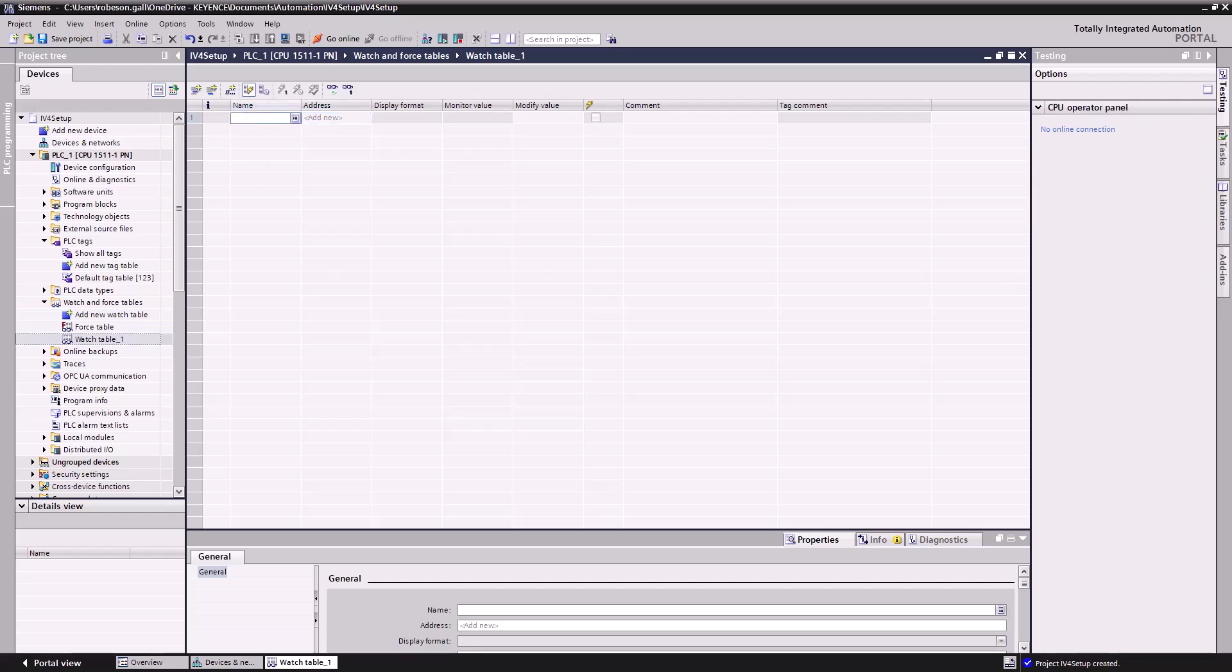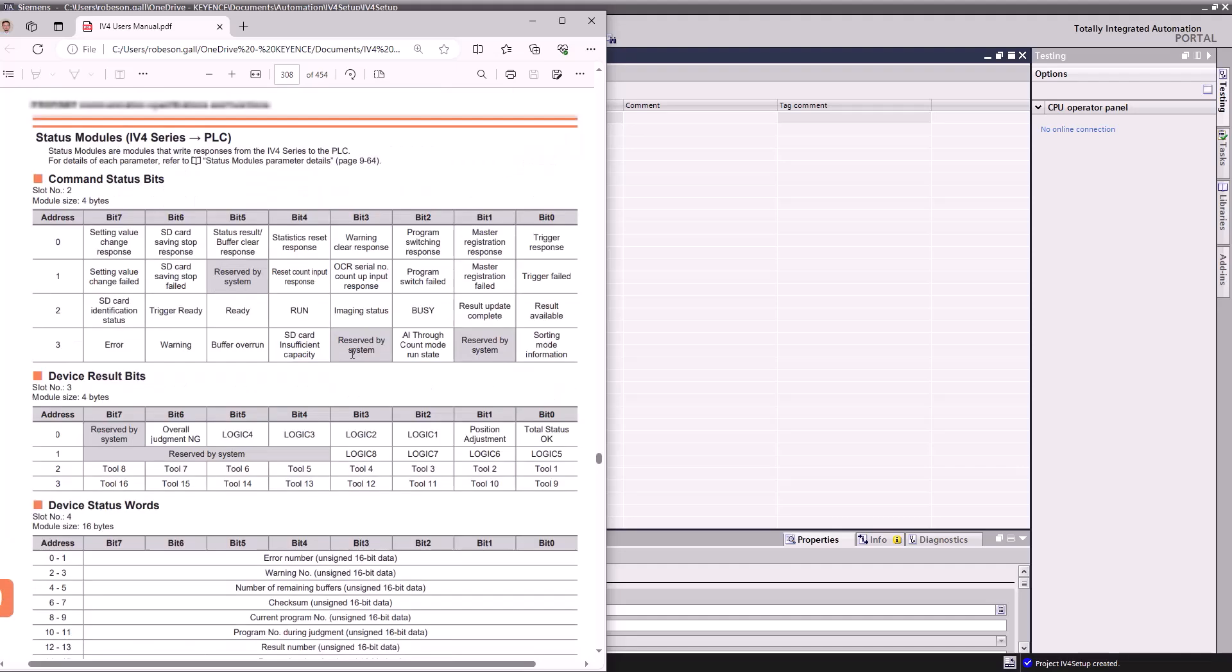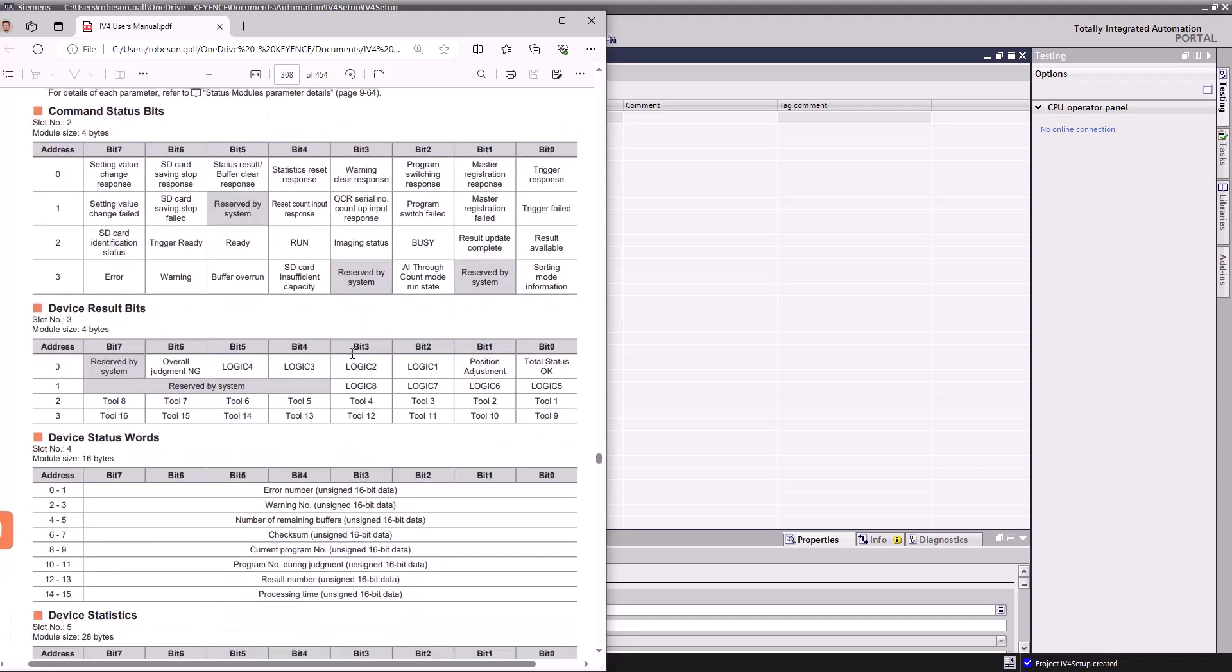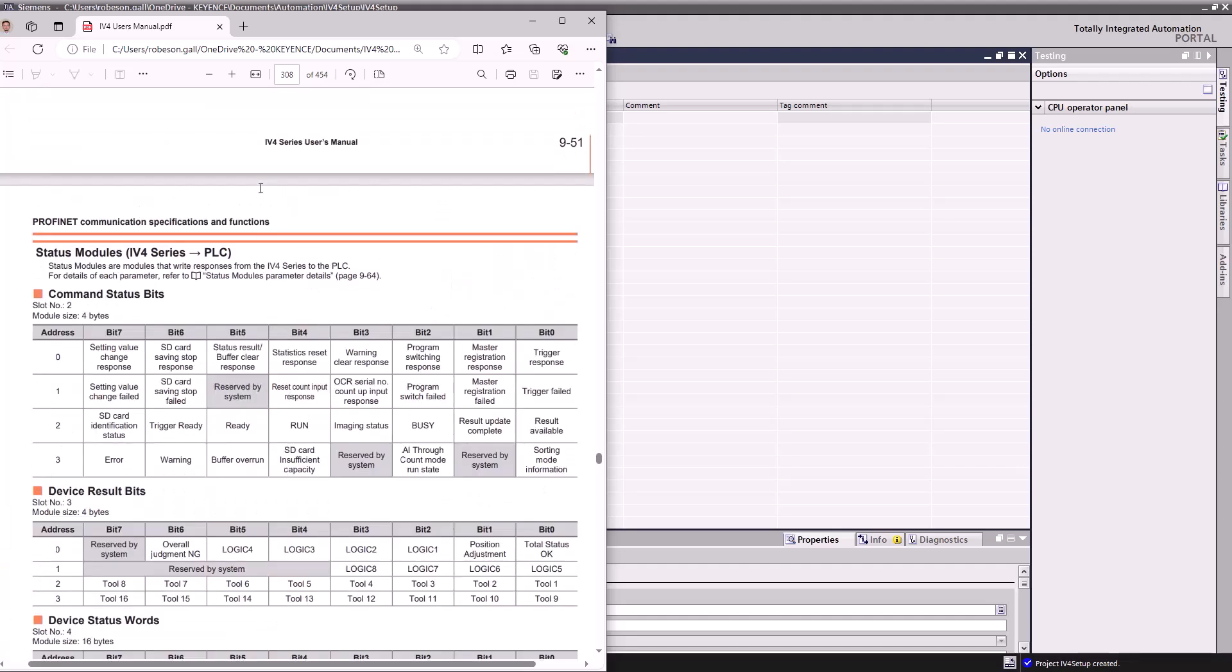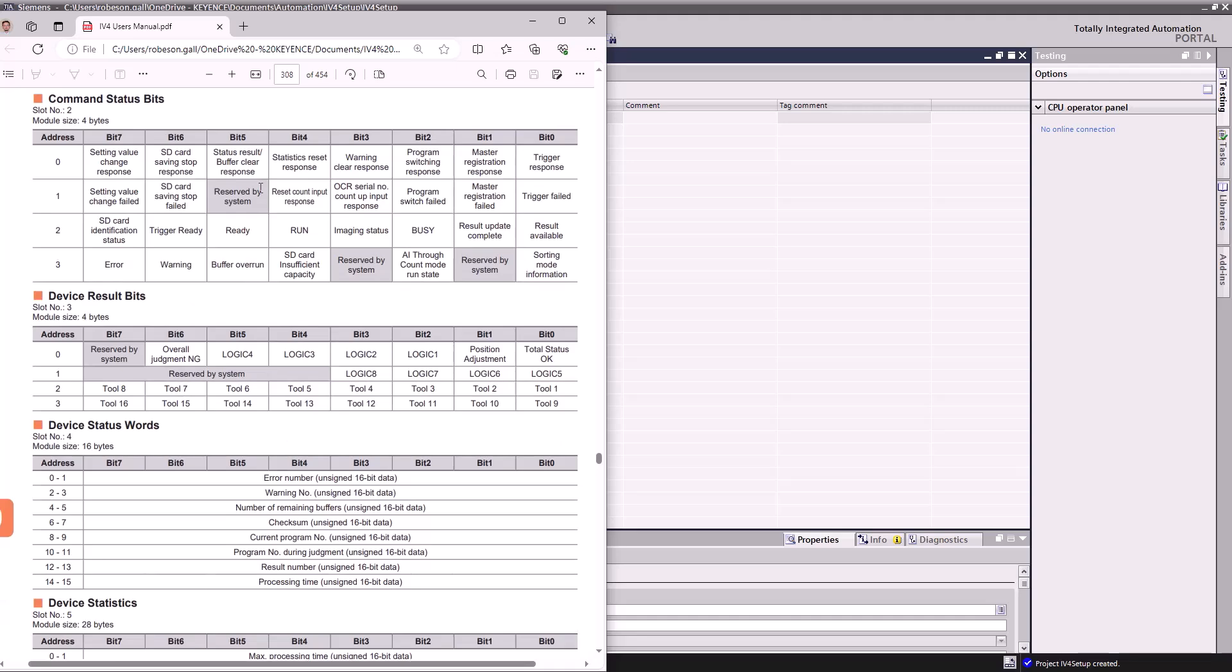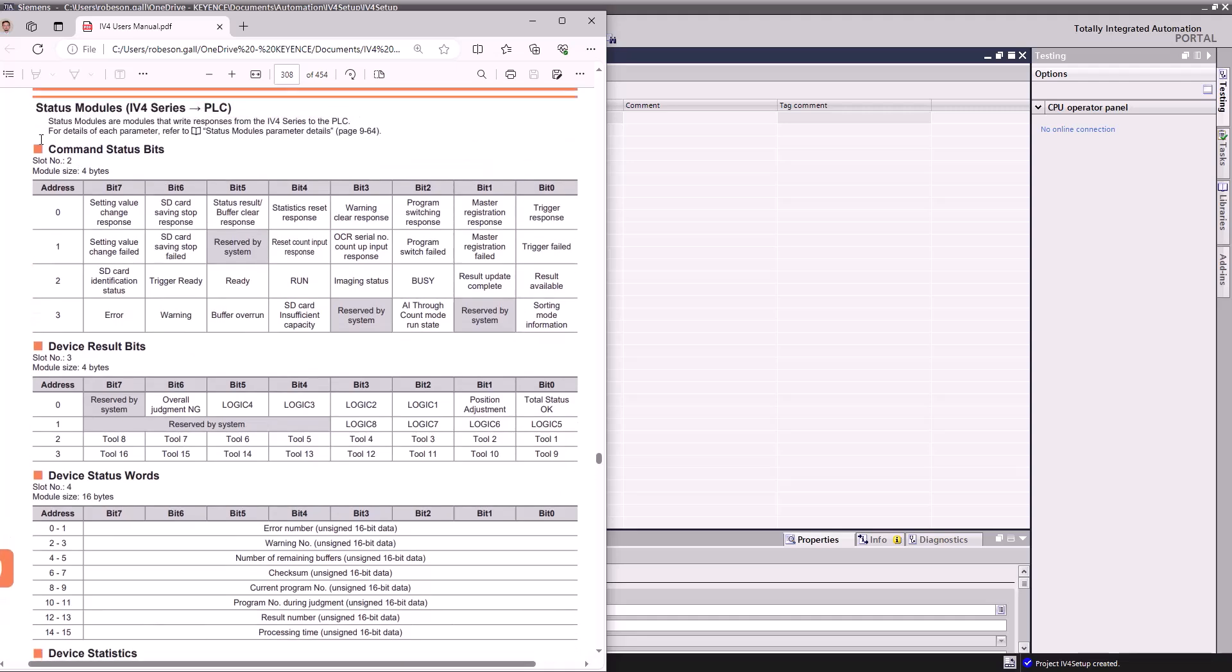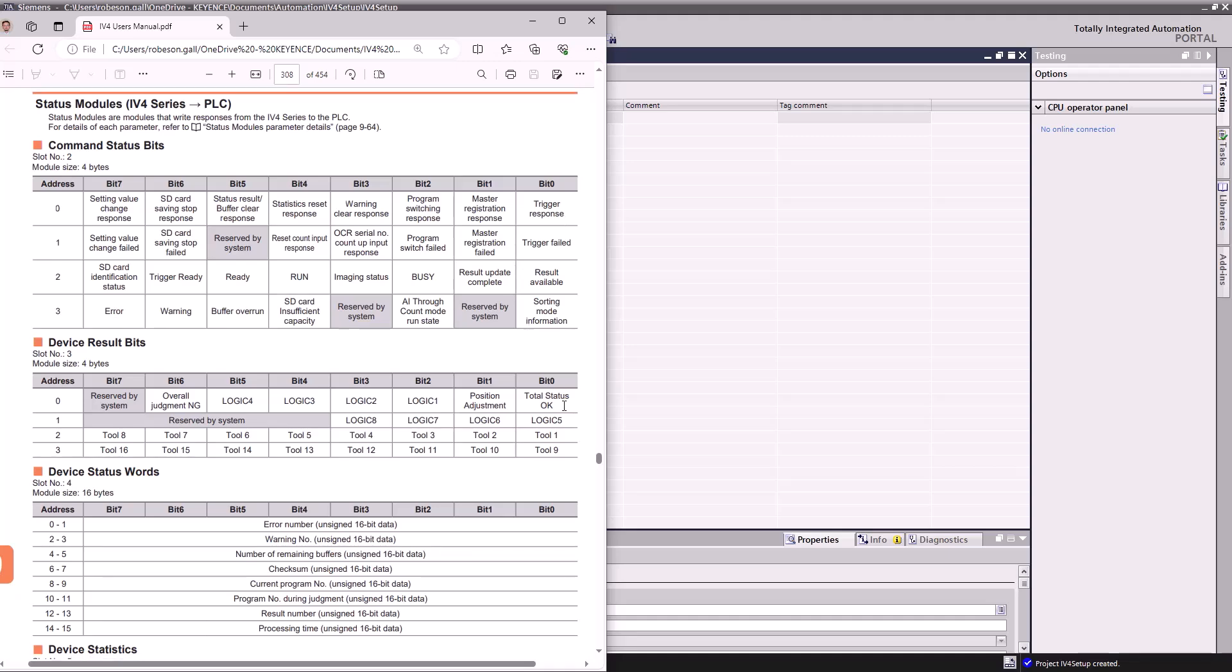When you're adding a new tag in here, you'll just want to make sure you reference the user's manual. And how these bits are laid out, so these are all of our inputs from the IV4 back to the PLC. So these are all those I addresses. I0.0, that's a trigger response that will come back every time you send a trigger. I'm going to grab our total status okay and our total overall judgment no good. These are sort of opposing bits, right? So one will be on when the camera gives you an okay judgment, the other when it gives a no good.